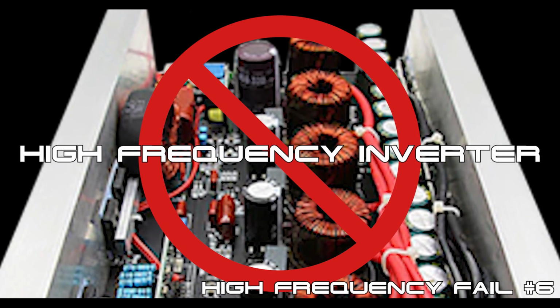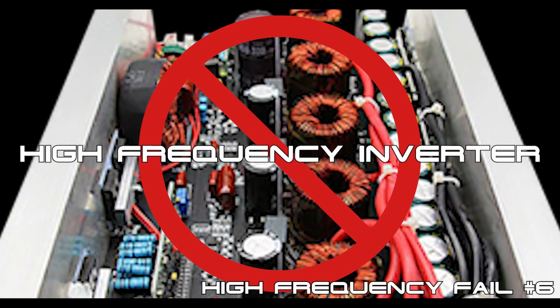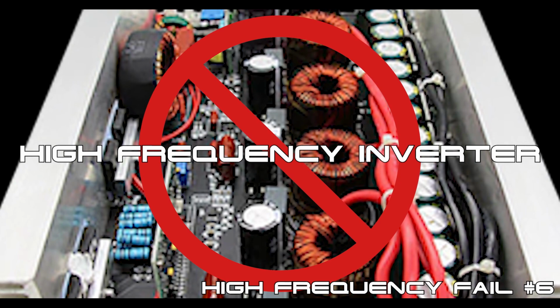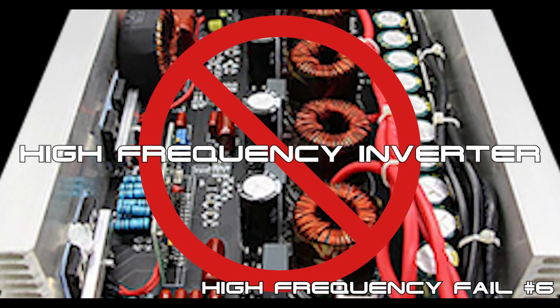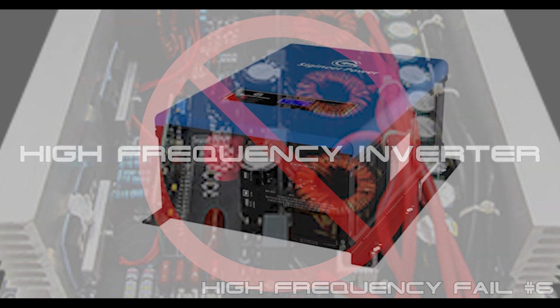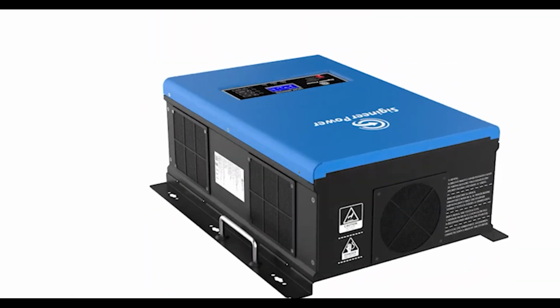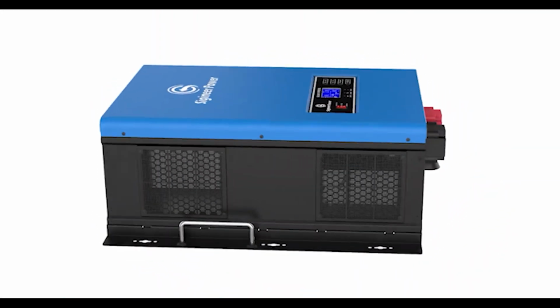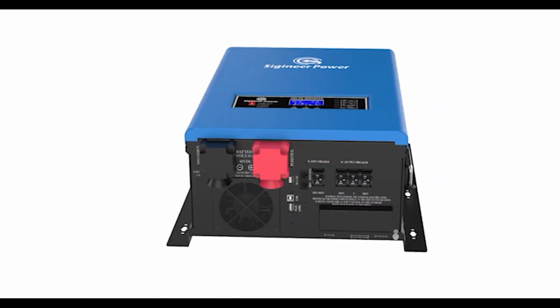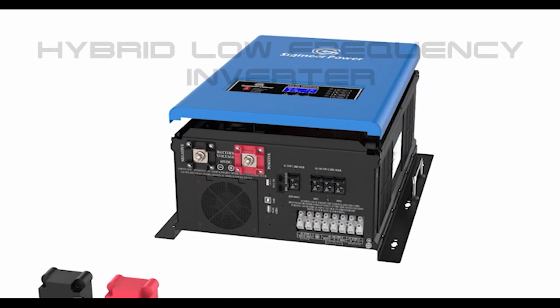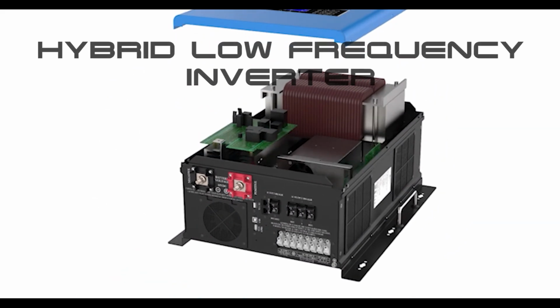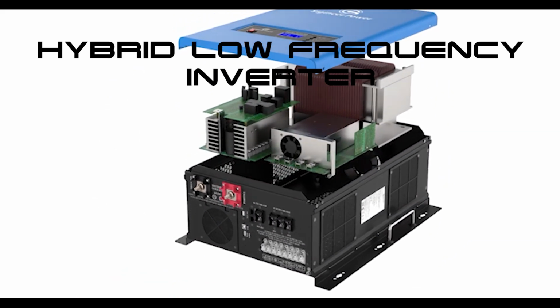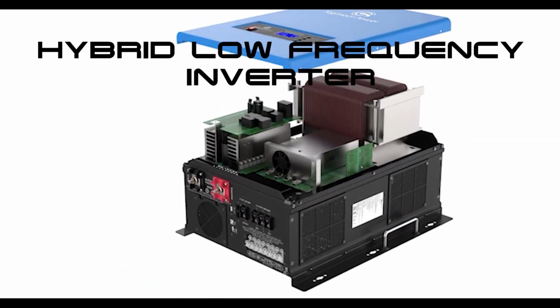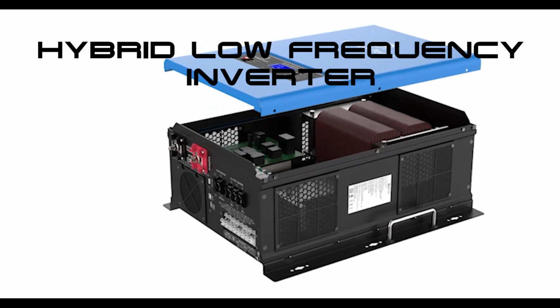With over 24 years in the inverter repair industry, it has been our experience that high-frequency transformerless inverters have a much higher failure rate compared to low-frequency, transformer-based inverters. So it is our recommendation that if you're planning on powering inductive loads in your home, such as microwave ovens, refrigerators, power tools, or AC units, you purchase a UL-listed, hybrid, low-frequency, pure sine wave transformer-based inverter charger.